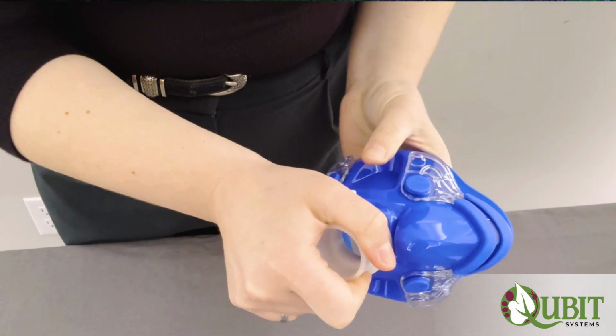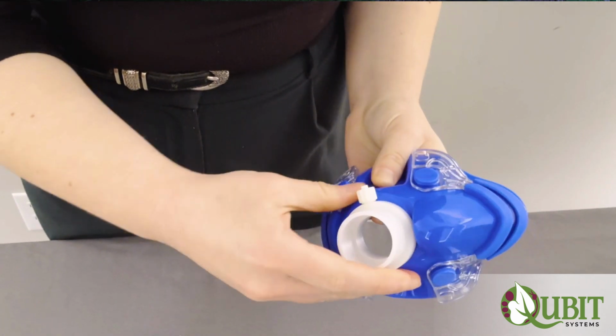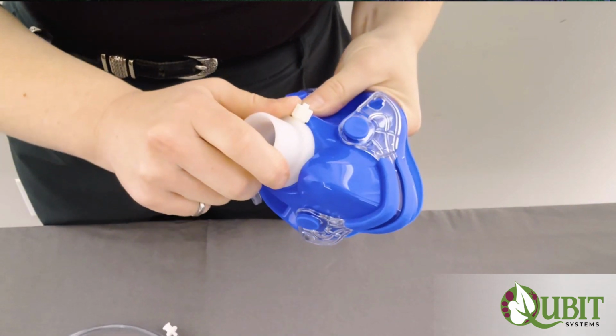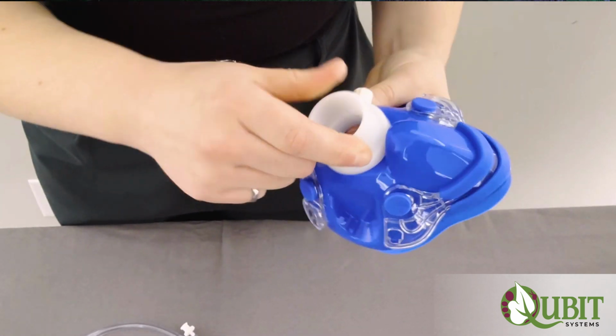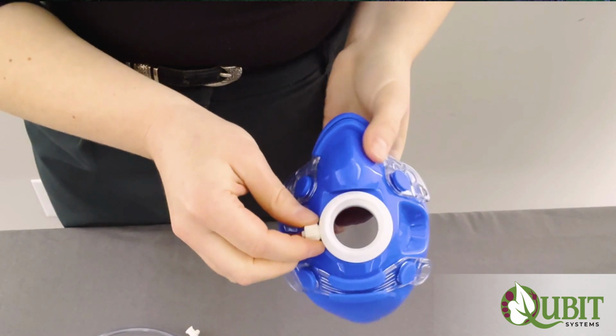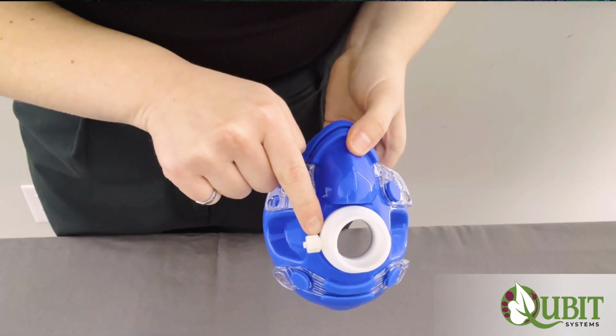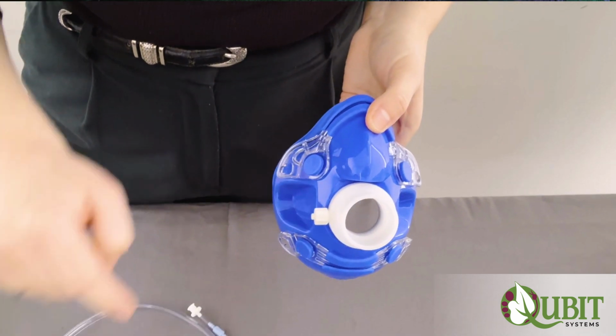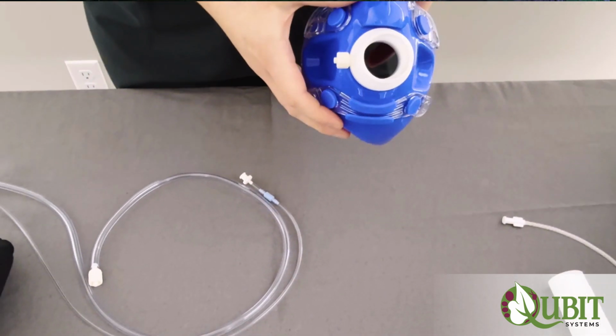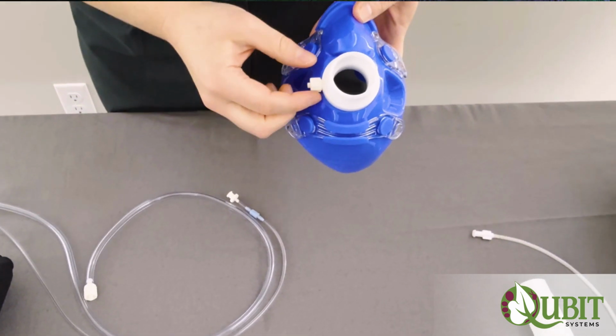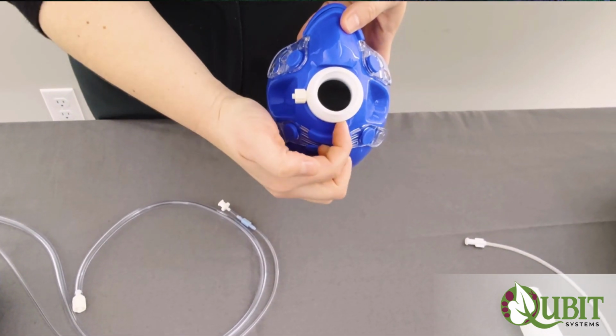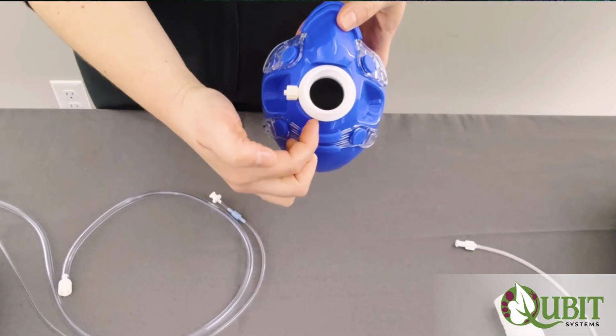It's important that the gas port on the side of the adapter faces outwards, generally to the side, and this will allow the air to clearly pull from the main flow of breath gas. It's important that the port does not face downwards, because then condensation could pool and plug the hole.